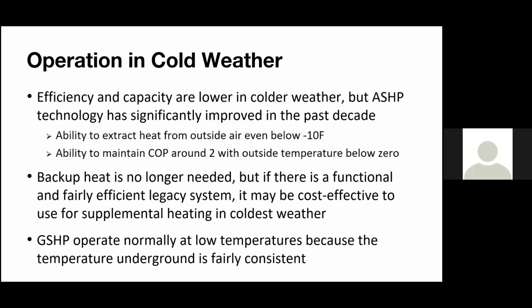However, if you do have an existing system, you could think about doing fuel optimization. Whereas, hey, it gets cold outside. I'm looking at my charts and my heat pump only has this COP and I'm paying this much for electricity, but I could just burn natural gas and it'd be a little bit cheaper, let's say, below 10 or below 0 degrees, whatever it is. And if you do have that existing system, that's fine, that works. Again, electrification is driving some of those factors, but right now that would be a perfect solution. The only thing to take away though is, VRF and new design does not need backup heat.